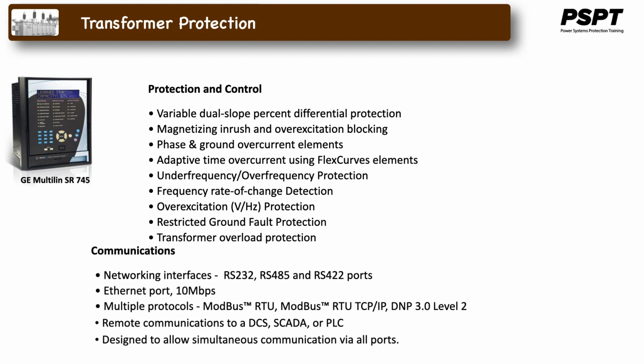This relay, as well as most modern IEDs, comes with communication capabilities that include network interfacing, RS-232, RS-485 and RS-422 ports. It has an Ethernet port for sample rates up to 10 megabits per second. It uses multiple protocols: Modbus RTU, Modbus TCP/IP, DNP, and several others. Remote communications to a DCS or a SCADA or a PLC type system, and it's designed to allow simultaneous communication via all ports.